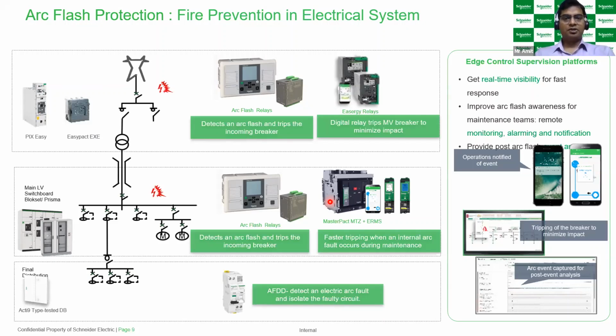And the last part: if you're talking about the room, how do you protect human beings, like in the patient room, OT, ICU, and how can you protect small kids from leakage or fire? There is a beautiful device called the arc fault detection device. Earlier, we saw the arc fault protection relay for 11 kV, 33 kV or 66 kV, the higher loads. Now we are talking about your own room or your own hospital, and how to protect from fire, which is a mandate for the US and European countries, like how in India we use RCCB, in a similar fashion they use AFDD as well. AFDD also works on the same technology as arc fault protection. If any arc arises, it automatically gives the command to the MCB, and finally your complete system will be isolated.